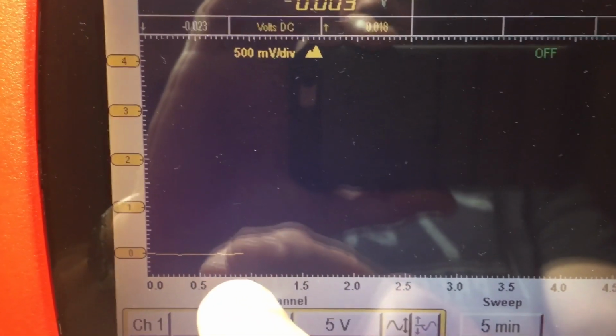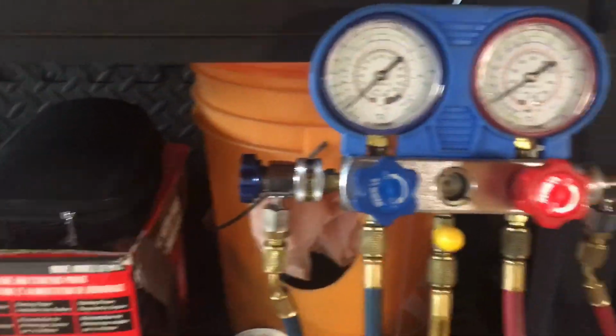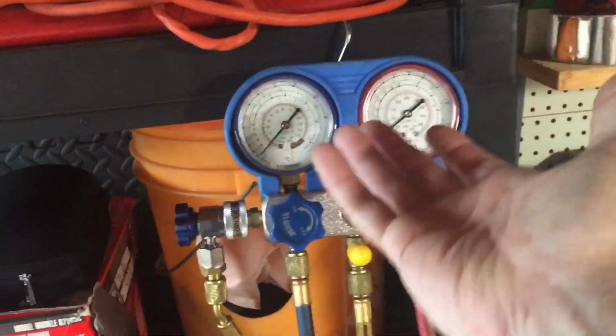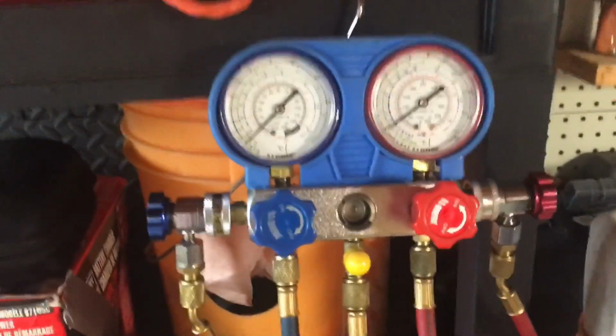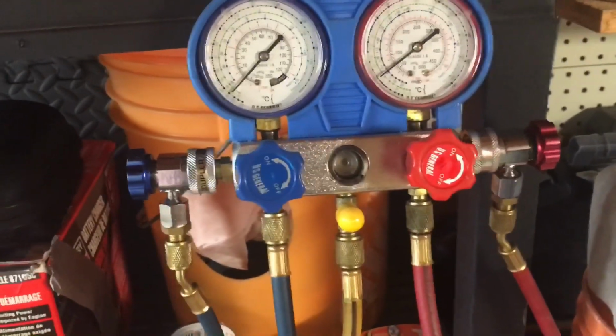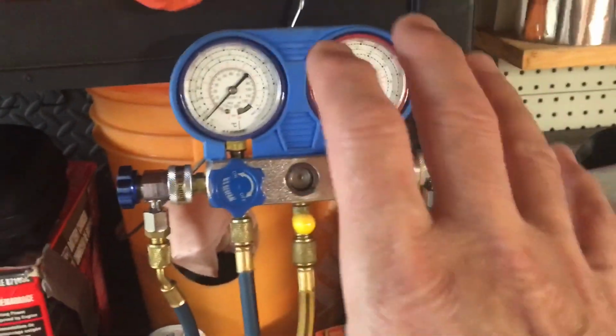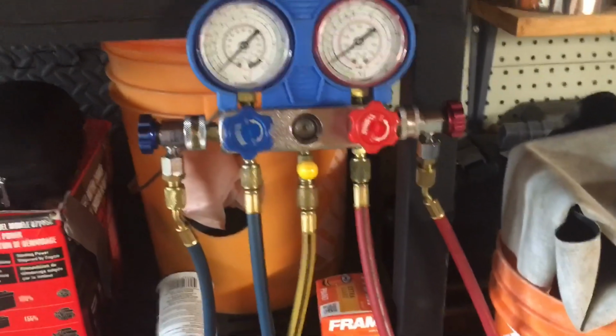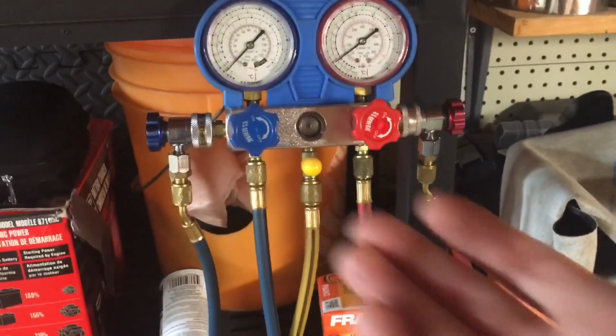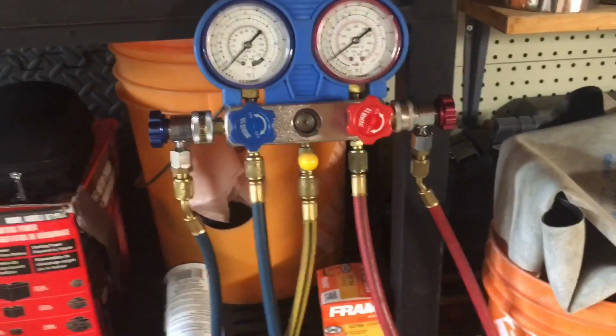As I said, we'll have a record of it, and not only that, the Schrader valve will be back in the service position. So unlike monitoring it with a gauge — these are only cheap gauges and the resolution is marginal anyway — there'll be a couple of advantages to removing the gauges from the system itself. One is, what if a leak presents in your manifold, the valving, and the service lines? Anyway, that's the idea, guys.